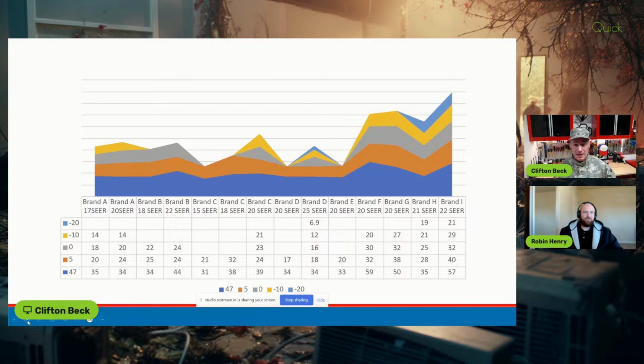We see some heat pumps that are high quality, not inexpensive, with lockout temperatures at positive 5 degrees Fahrenheit - they don't work below that. Then you could switch to another manufacturer whose unit runs all the way down into the minus 20s with good performance. So it's moved from being a brand-preference contractor to being a product-knowledge-base contractor.